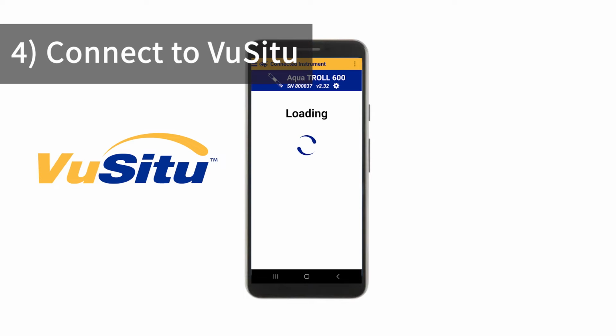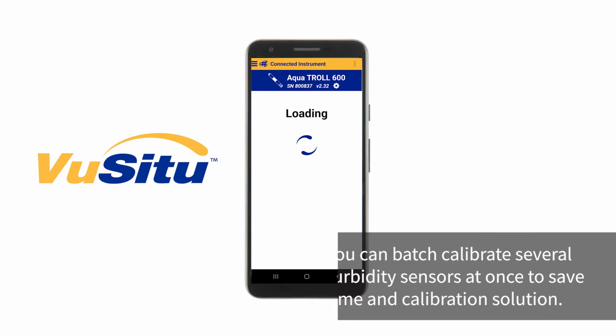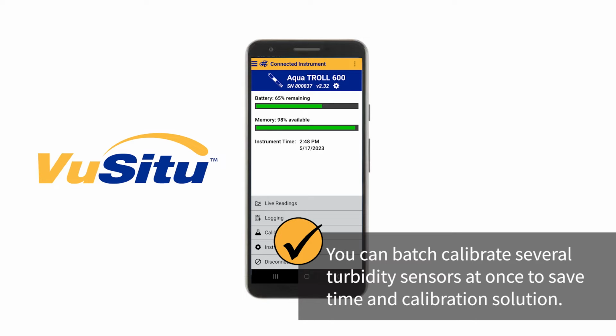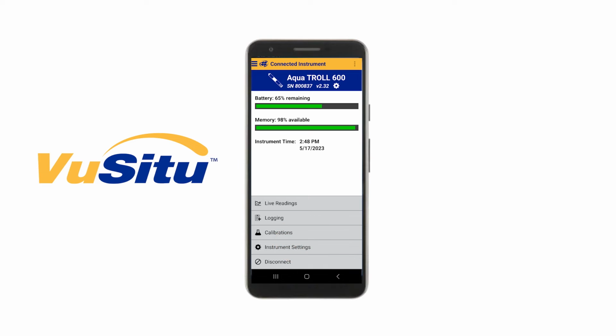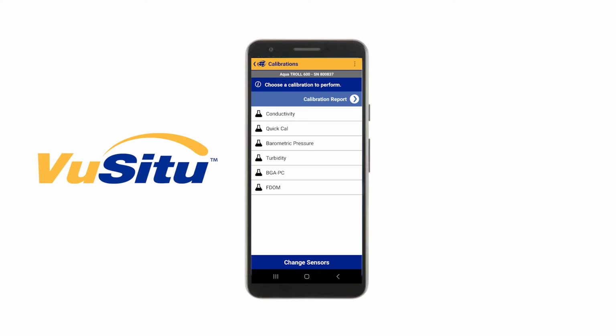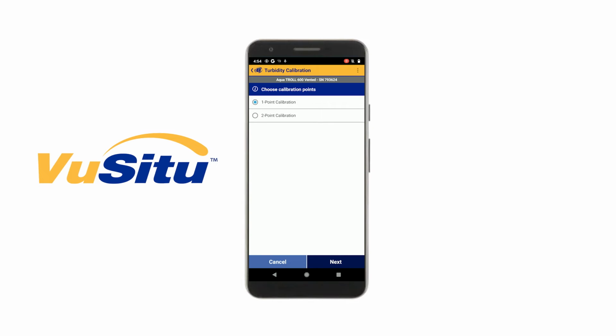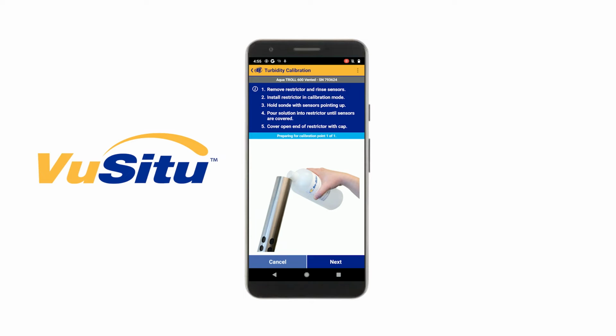You can batch calibrate several turbidity sensors at the same time to save time and reduce the amount of calibration solution you need. I'll include a link in the video description if you'd like to know more about the batch calibration process. Tap Calibrations, then choose Turbidity. Since turbidity is an optical calibration, the rinse that we did with water earlier is sufficient.